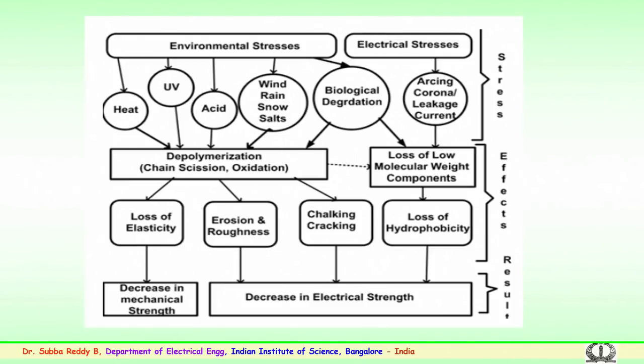Electrical stresses, as mentioned, include arcing on the surface because of the formation of dry or wet bands. Over a period of time, or during monsoon conditions or early morning conditions where fog, mist or snow is on the insulator surfaces, along with the pollutants and contaminants, the surface starts conducting because of the non-uniformity of the coating or the pollutants collected, and also due to wind conditions. The surface becomes conducting in some portions and not in others. Where dry band or wet band formation happens on the surface, small arcings or partial arcs do happen.